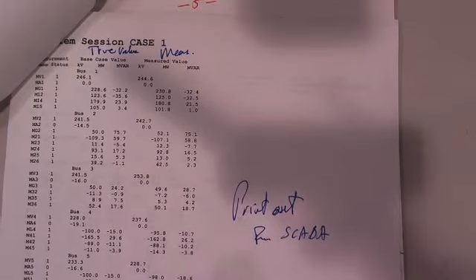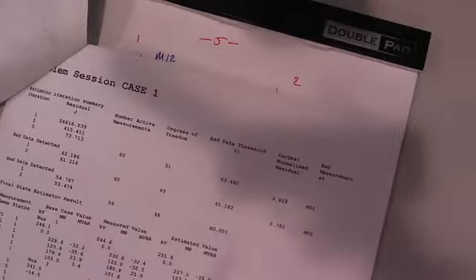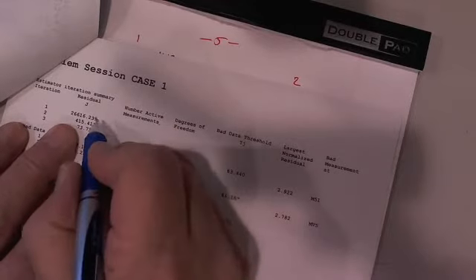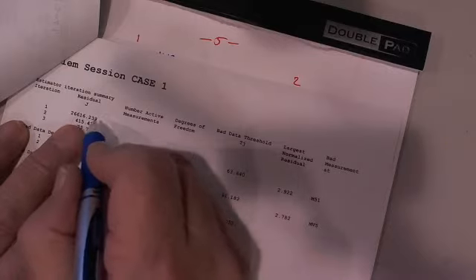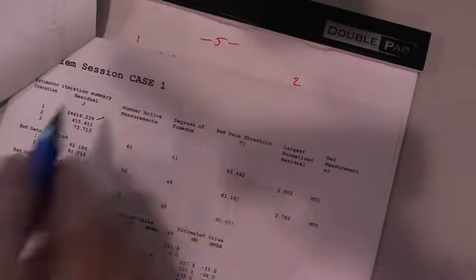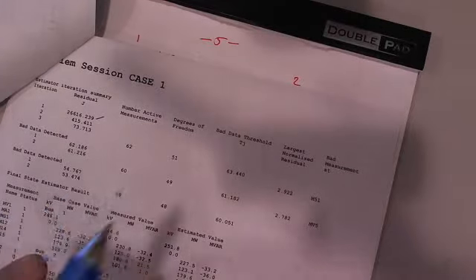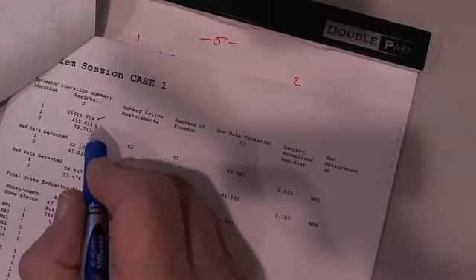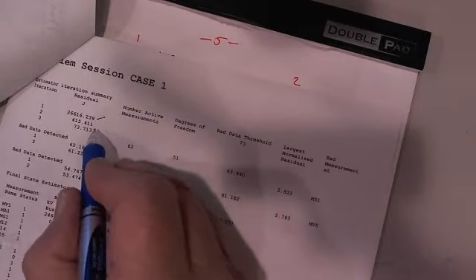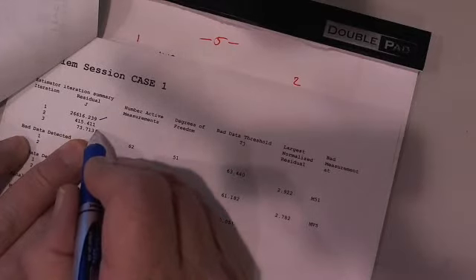Okay, and again it stops, and you put your cursor down here and hit return, and it starts going, and it gives you that thing. It says, do you want to do bad data detection or not? Now I didn't purposely put any bad data in here, but here is the first execution of the state estimator. It starts out with J of 26,616. That's starting from the voltages and phase angles are like 1.0 and 0 degrees, and then it converges to 73.713.